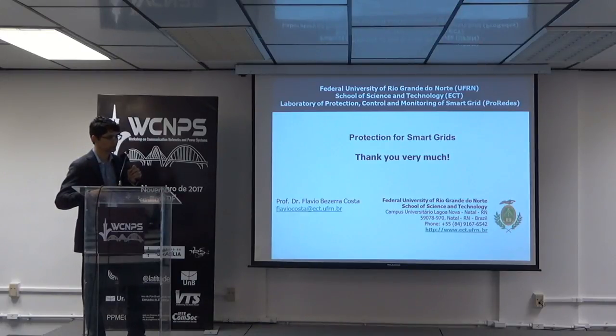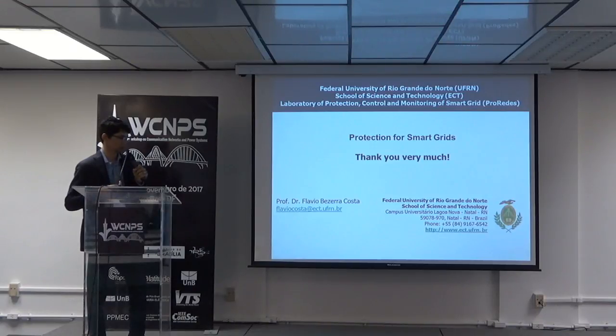However, if the goal is to detect the fault by using traveling waves, for instance, a high sampling frequency is necessary. And the wavelet transform can be used with a high sampling frequency because the wavelet transform presents a good time frequency relationship, and it's possible to detect low frequency transients as well as high frequency transients. So by using traveling waves, a sampling frequency in the order of megahertz is necessary.